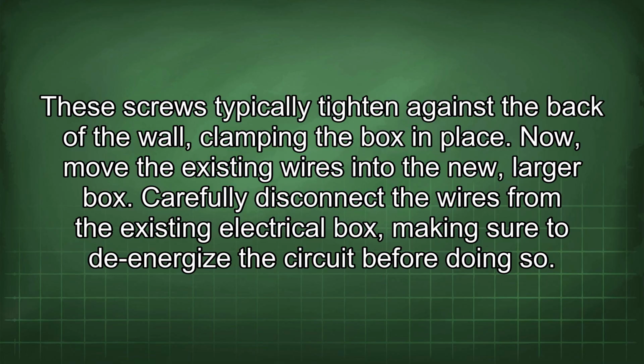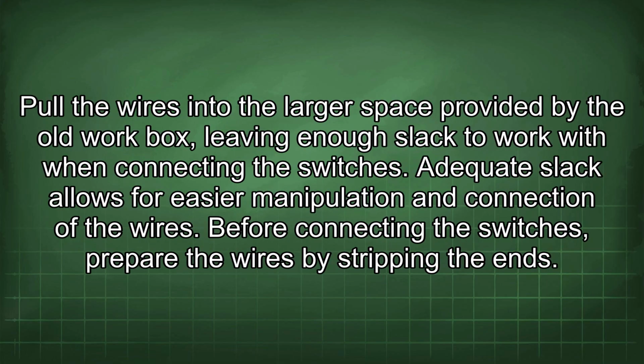Now, move the existing wires into the new, larger box. Carefully disconnect the wires from the existing electrical box, making sure to de-energize the circuit before doing so. Pull the wires into the larger space provided by the old work box, leaving enough slack to work with when connecting the switches. Adequate slack allows for easier manipulation and connection of the wires.